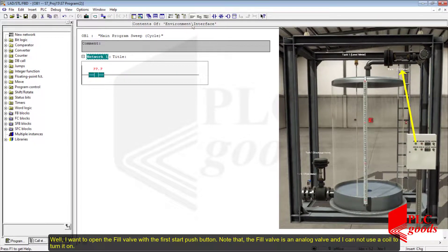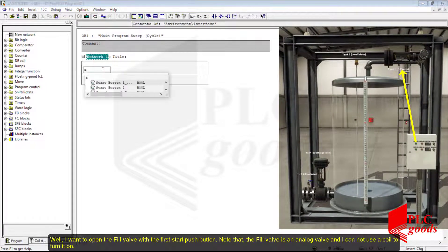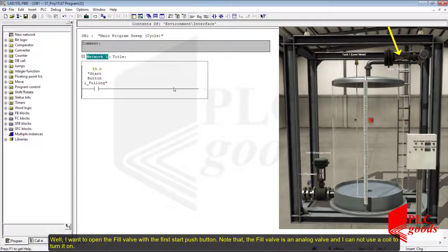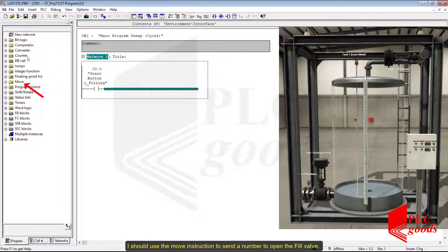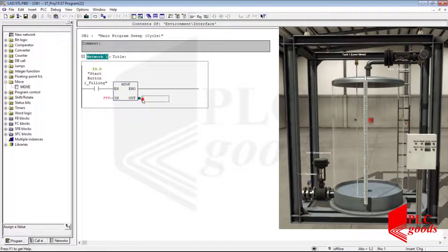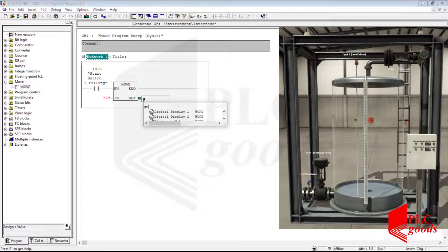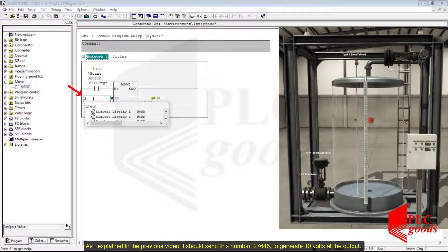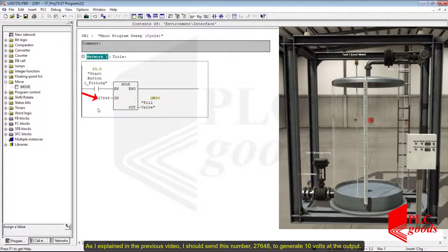I want to open the fill valve with the first start push button. Note that the fill valve is an analog valve and I cannot use a coil to turn it on. I should use the MOVE instruction to send a number to open the fill valve. As I explained in the previous video, I should send the number 27,648 to generate 10 volts at the output.